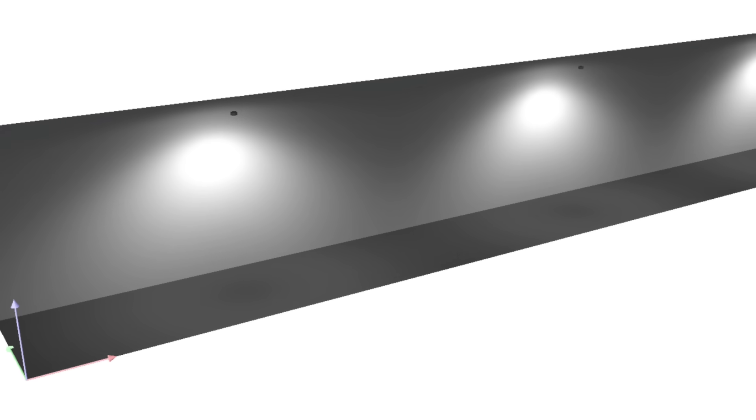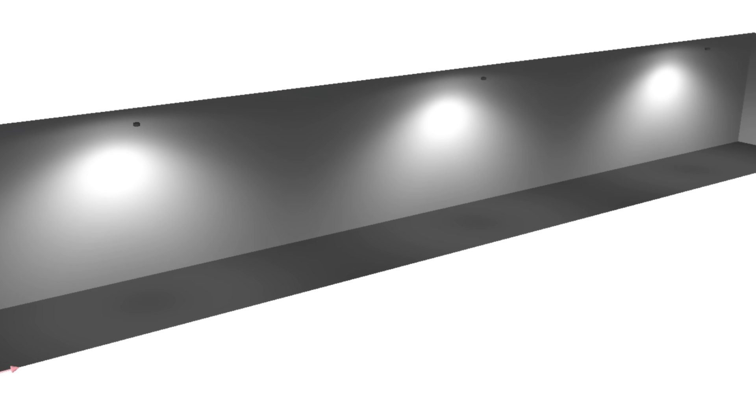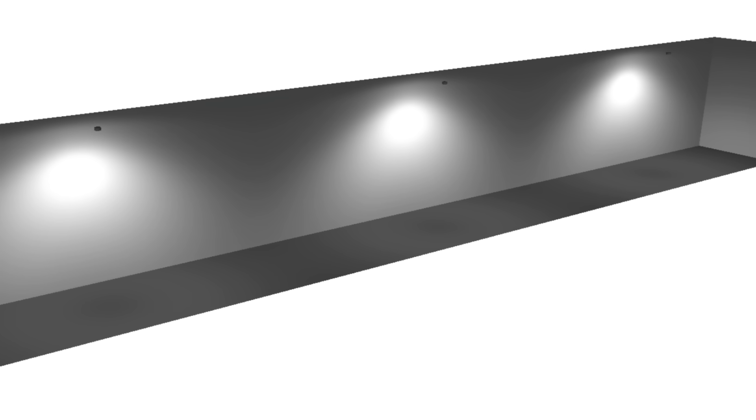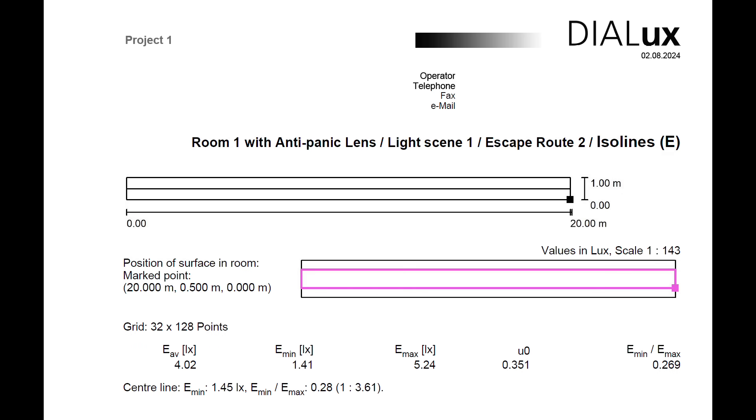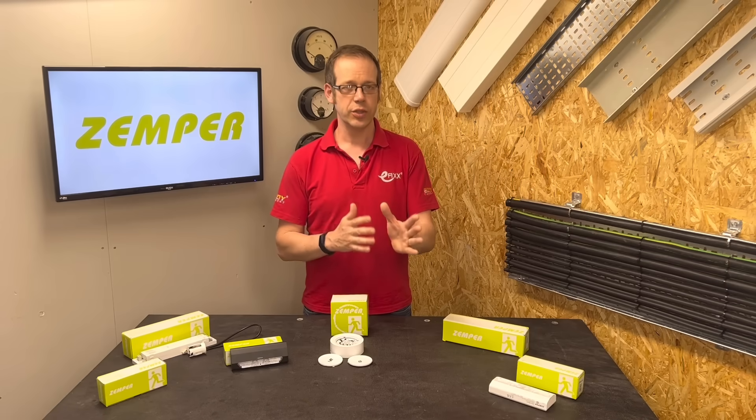In this version, I've inserted enough fittings to illuminate the escape route. You can see the bright patches on the walls from the circular spread of light that we'd get if we used the anti-panic open area lens. Looking at the results of the calculation, you can see that down the central line of the escape route, the lowest value is 1.45 lux — above the 1 lux minimum — and the lowest value along the 1 metre wide central band of the corridor is 1.41 lux. We haven't mentioned the uniformity value so far, but suffice to say they're well within the acceptable limits.